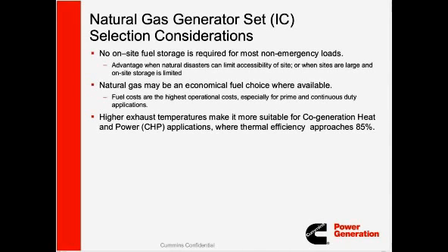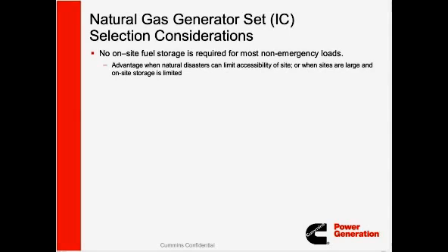Natural gas generator sets for internal combustion selection considerations. Basically, the benefit there is no on-site fuel storage required for most non-emergency loads. The advantages are basically there when you have natural disasters where you have limited access to the site. It may be hard to refuel the diesel generator sets. Another thing is for large sites, on-site storage is limited, so it may be better to use a natural gas generator set. Natural gas also may be economical fuel, especially for non-emergency and non-standby applications.